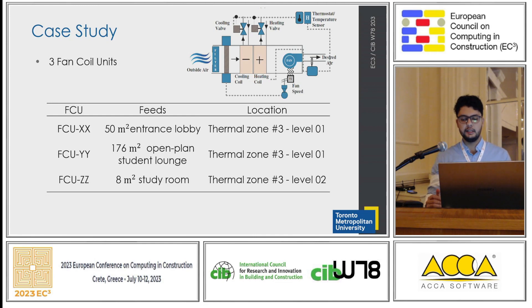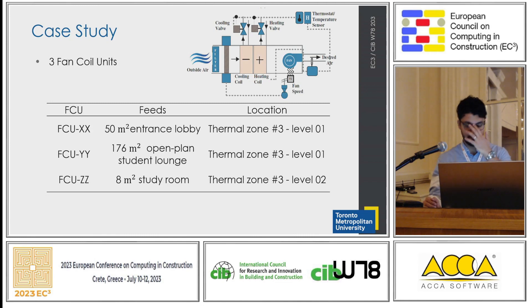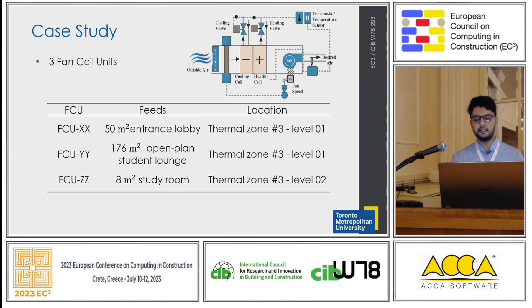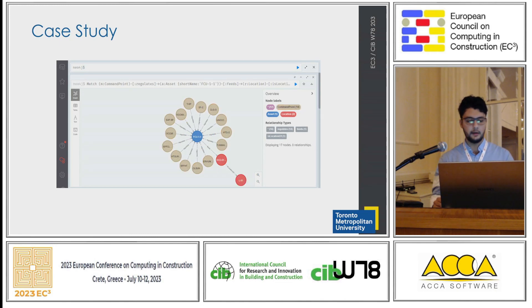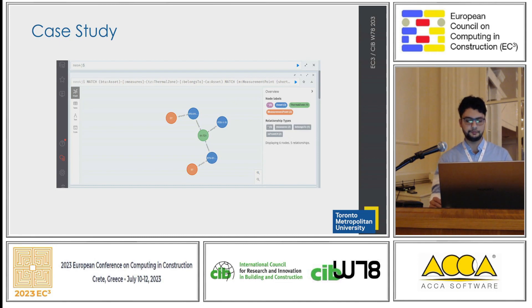Fan coil units are widely used as terminal units in HVAC systems in buildings, and are the final piece of equipment through which air passes before it is delivered to the conditioned space. Sometimes if you look up, you can see them. Data were sampled from FCU-XX, FCU-YY, and FCU-ZZ year-round during peak heating in December 2019 and peak cooling in June 2020. FCU-XX is the one without a fault, used for initial testing. We requested our graph-based database to provide various data related to measurement points, command points, and other variables affecting FCU performance, like hot water and chilled water temperature supplied to each zone.